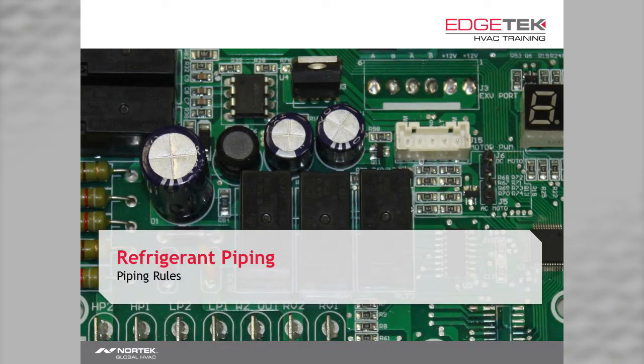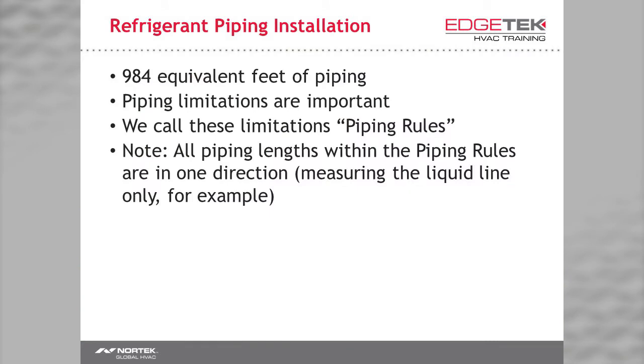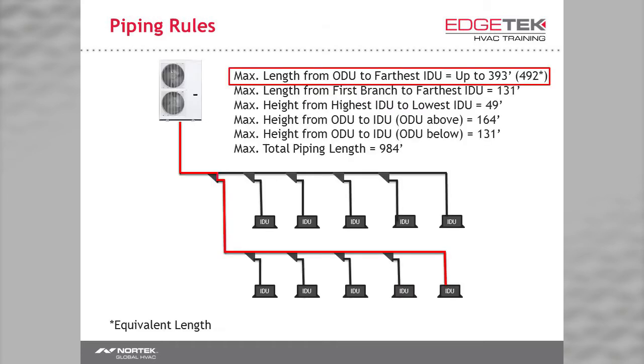So let's talk about our piping rules. All of the measurements we will use henceforth are in one direction. In other words, if you were to just measure the liquid line length, that's the length we are using. Our first entry is our maximum length from our outdoor unit to our farthest indoor unit. This is up to 393 feet actual and 492 feet equivalent.